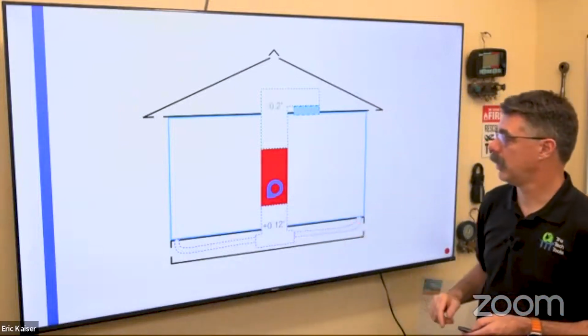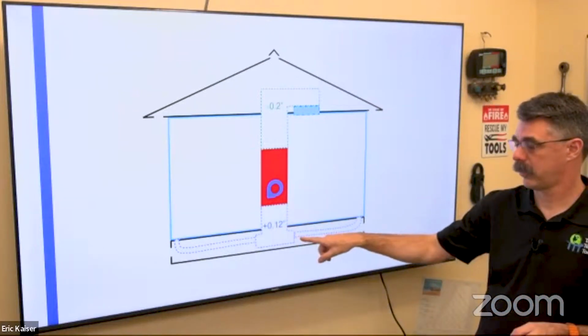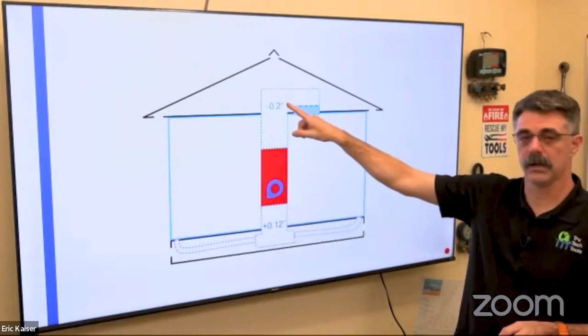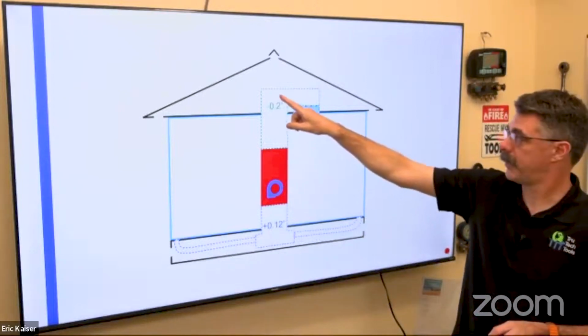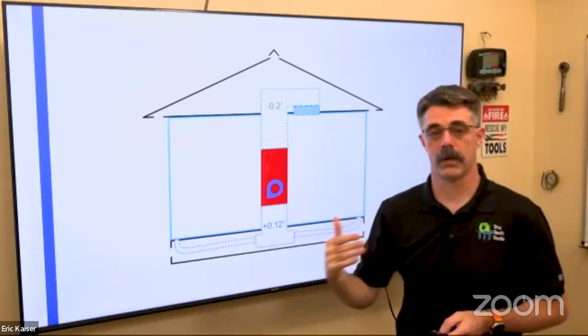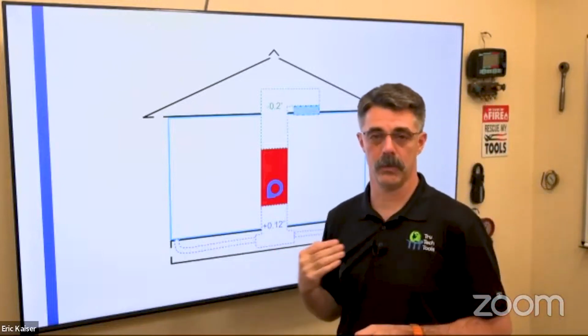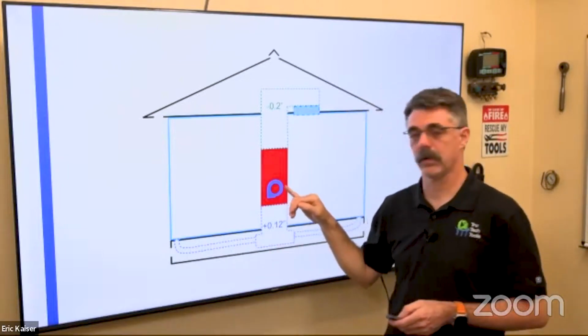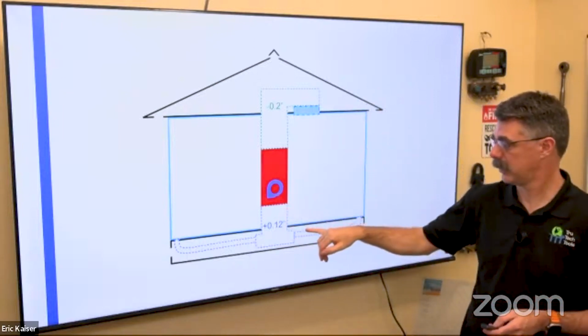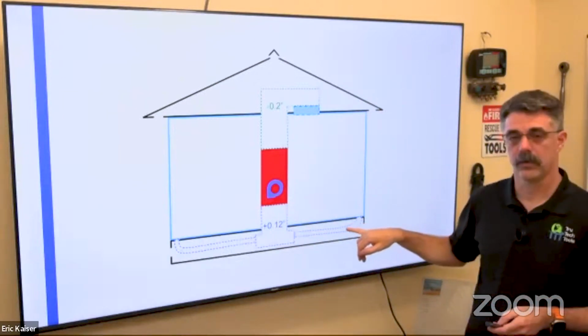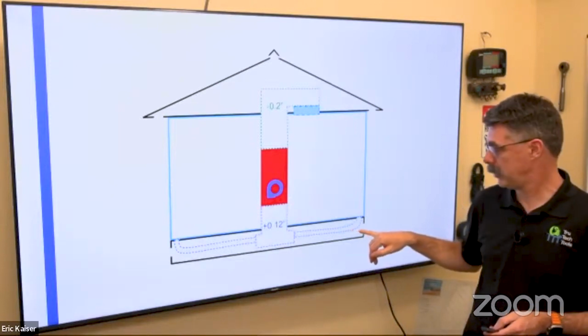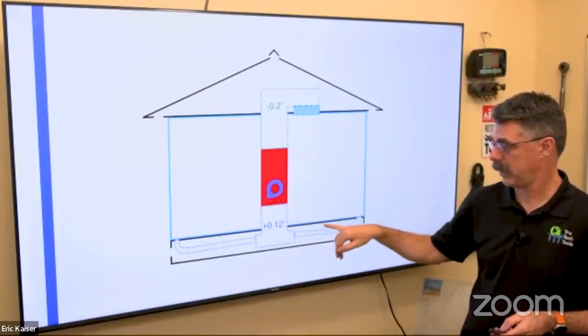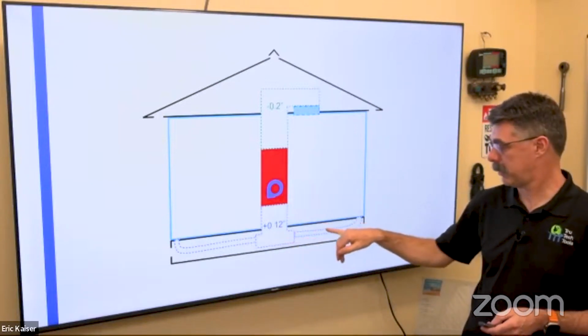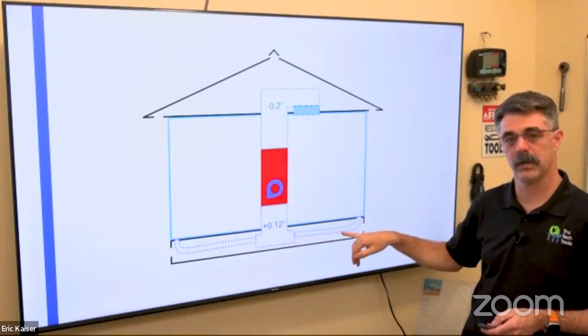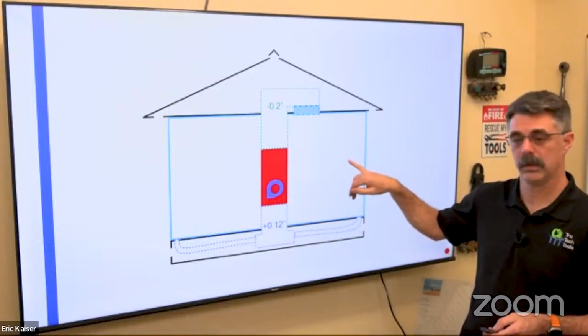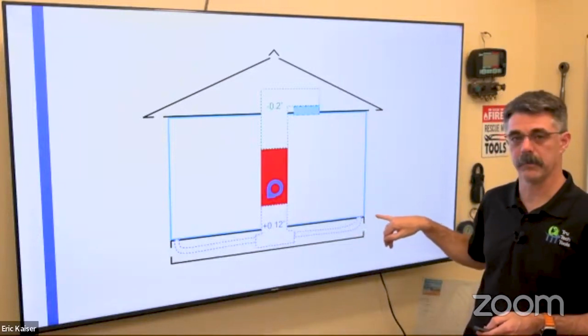And what we're going to do is put a fan in there and create pressure here and pressure here. And if there's any leaks in that ductwork, pressure differential makes air move. That's how we get air moving from point A to point B. So the fan creates pressure differential inside those ducts. And now we can move air from outside. If this duct down here, being the supply duct, leaks, it's going to blow air into the crawl space, which isn't going to go back into the house. It's going to blow out these vents over here.